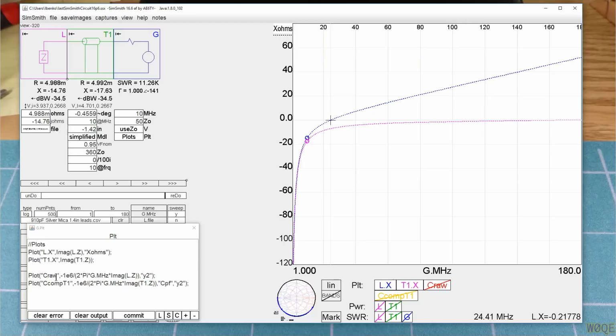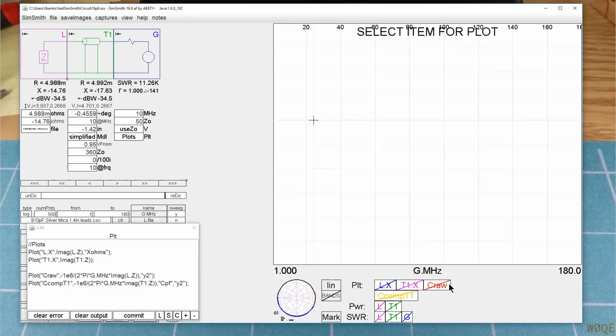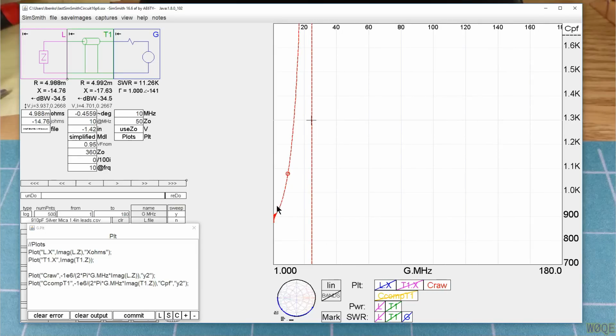Now we're also going to plot the capacitance. You know that X sub C is 1 over 2 pi f C, so C is 1 over 2 pi f X sub C, and that's exactly what this is plotting. But we get frequency in terms of megahertz, not hertz, so we have to multiply by 1 times 10 to the 6th here. And since reactance is a negative value, we don't want to show capacitance as negative, so we put a minus sign in front. And if we do that, we see the raw capacitance being what it was before. It started off down here at 900 picofarads, went up out of sight, and came back down. It was inductive, which was unfortunate. After we compensate for it, we get this curve. It starts at around 900 picofarads and stays close to 900 picofarads up through 50 megahertz or so, indicating that we compensated for it pretty well.